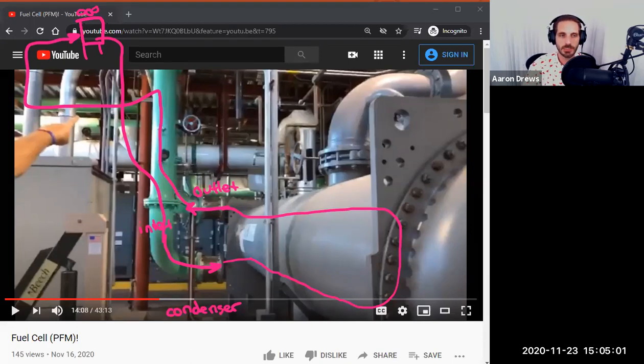The other fluid that is flowing inside of here is whatever our refrigerant is. I think Tom said that the refrigerant in here was R134A. But don't quote me on that because I don't remember exactly what it is. That refrigerant is flowing down through here and it's running over the outside of these tubes. That's occurring in what we call the shell. Remember, there's thousands of these tubes, but eventually that coolant gets cooled down. It started off warm up here and it gets cooled down a little bit more over here and eventually comes out through the bottom on this side. So this is our condenser.